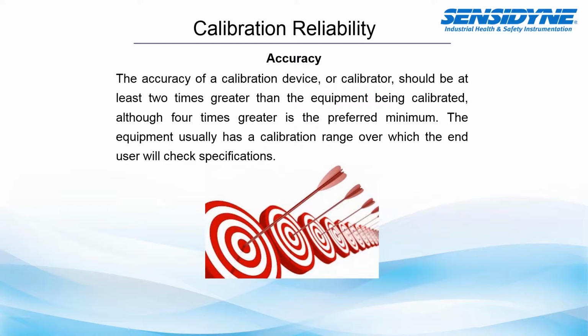An example of this would be if I need to make sure that I am plus or minus 5% within my set flow rate, I would want to make sure that I'm using a minimum of a 2% accurate calibration device, but a 1% accurate calibration device, known as a primary standard, would probably be my preferred calibration device.